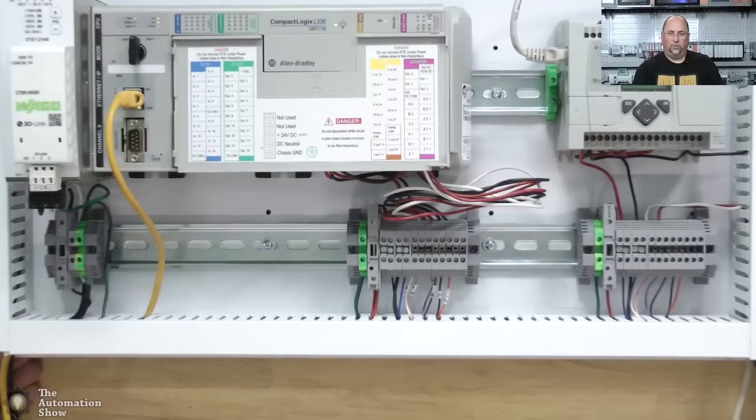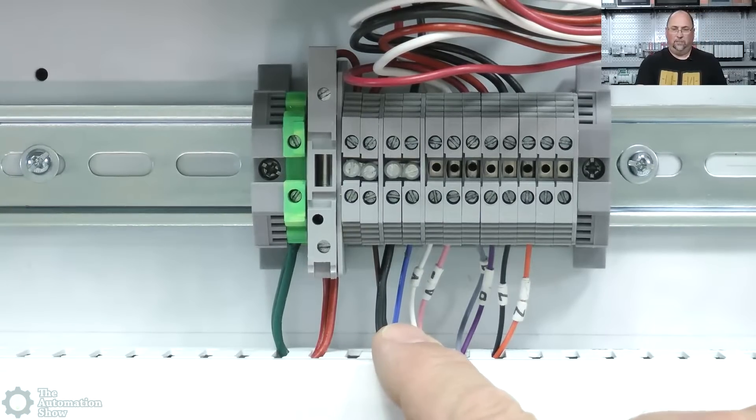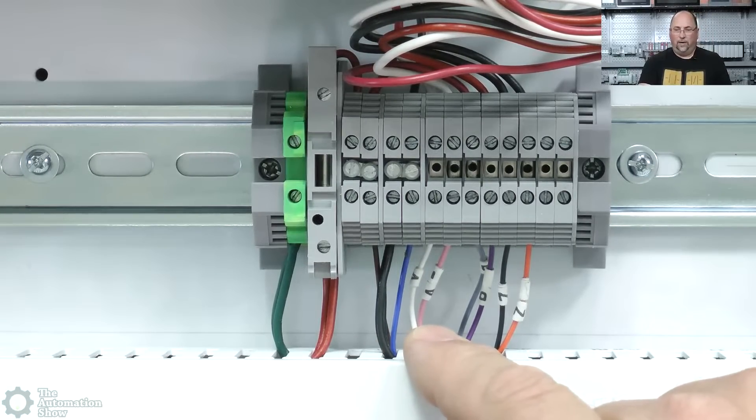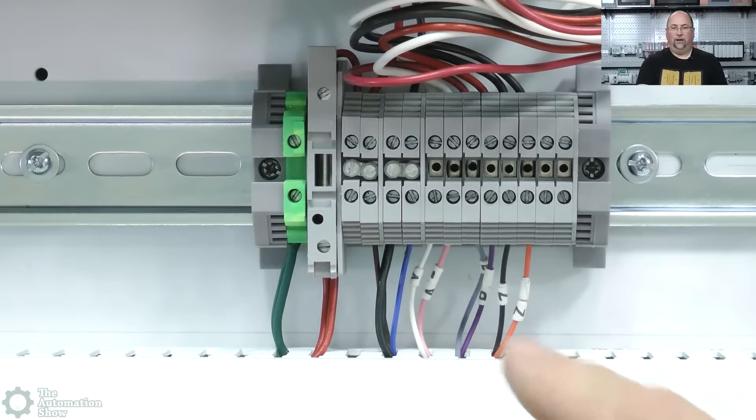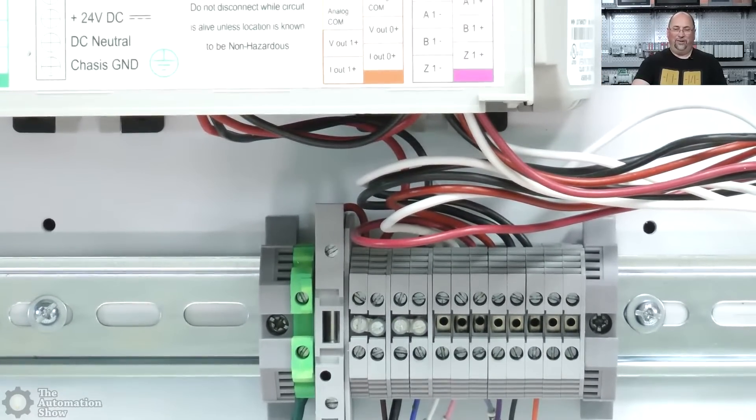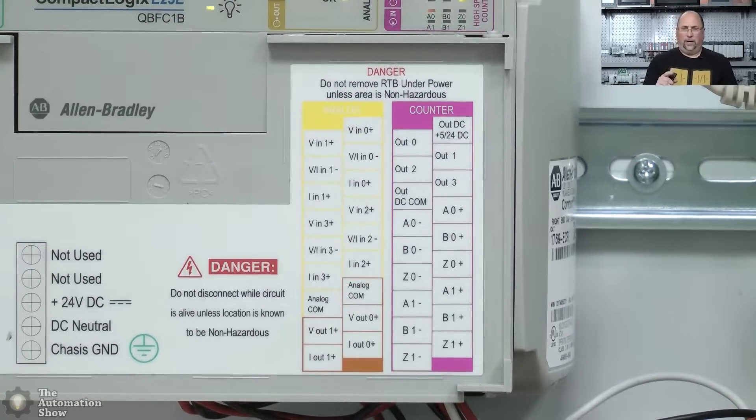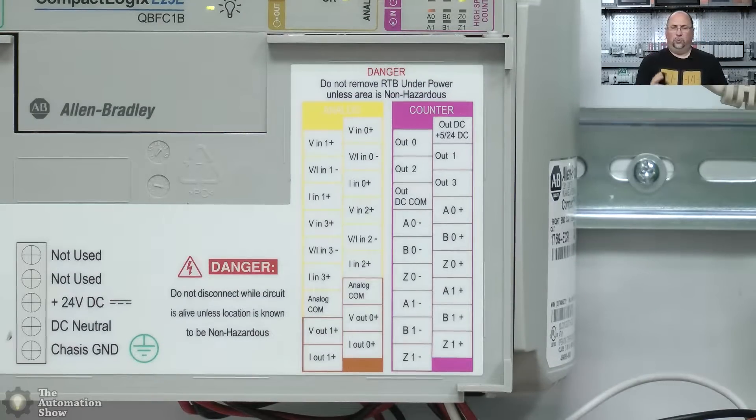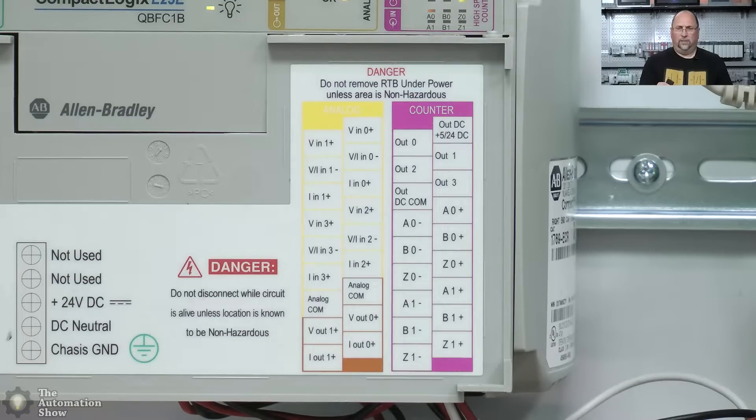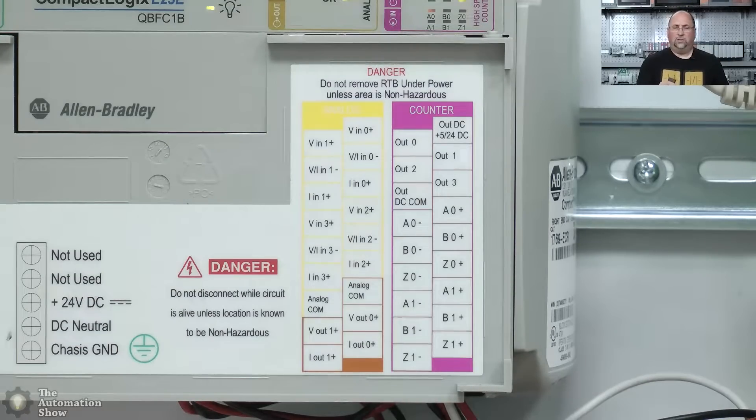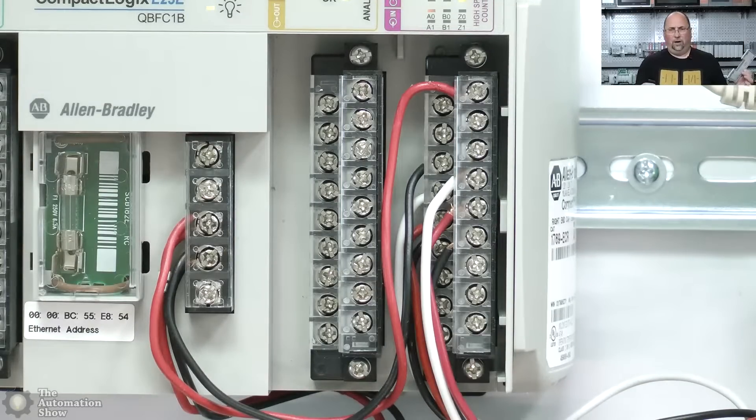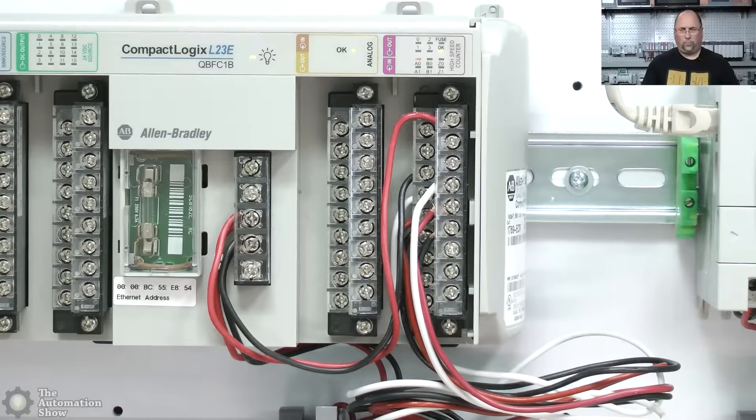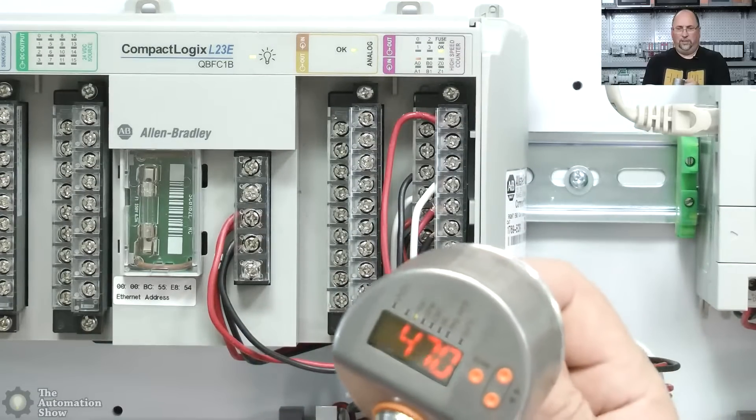Let's go ahead and zoom in here and take a look at the wiring. We'll start with the encoder wiring. You can see here, we've got the brown, which is DC plus, the blue which is DC minus, the white which is A, the pink which is A minus, the gray which is B, and then the purple which is B minus, then we have Z and Z minus here, black and orange. I didn't have all those beautiful colors, but let me show you where that wires into. I've taken the cover off to show you where A0. This has two counters on it or two quadrature encoder inputs on this counter module. So that's built into the L23. You can see here, we're using counter zero, so we're using A0 plus, A0 minus, B0 plus, B0 minus, Z0 plus and Z0 minus.